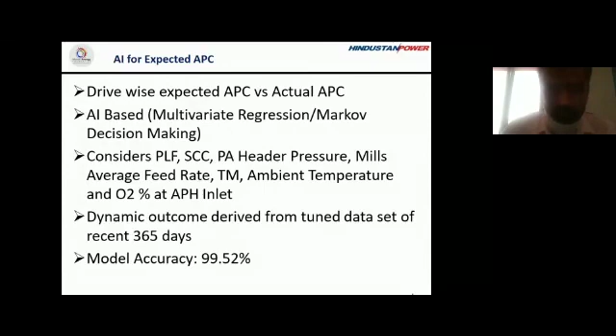I'll take you to the snapshot of the results we received. These are the coefficients. In a regression-based model, the expected APC can be thought of as dependent on some independent variables, like PLF, specific coal consumption, header pressure, mill's average feed rate, and so on. Based on this table, the APC can be derived by this formula on a regular basis.